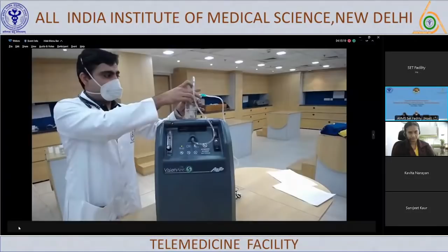We have connected it to the electricity, and now I'm switching on this button. Once you switch on, it gives an alarm, which is for low oxygen, but within 1 to 2 minutes this alarm will disappear because the oxygen concentration will rise above the lower limit, which is around 80% for this machine. Then we open this flow meter to the desired flow. Here it can go up to 5 liters per minute. And we can see the bubbling in the humidifier water, and this can be applied to whichever patient needs oxygen.